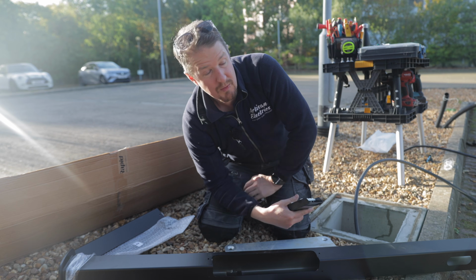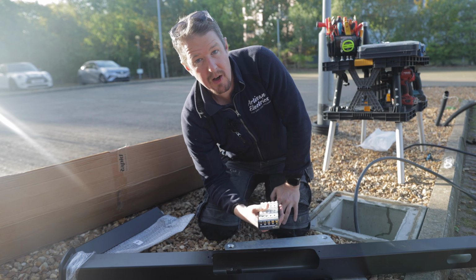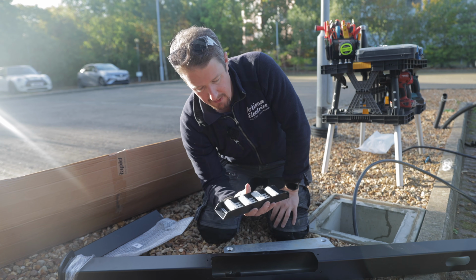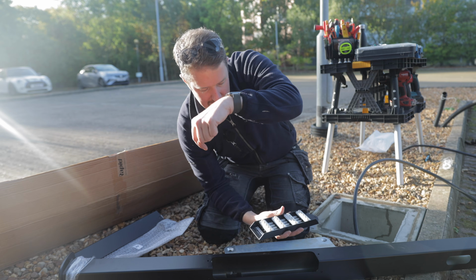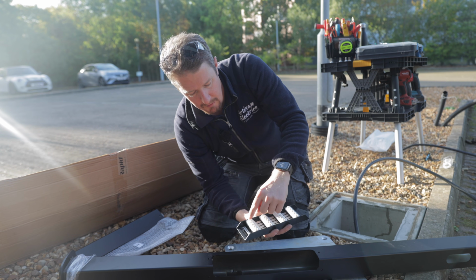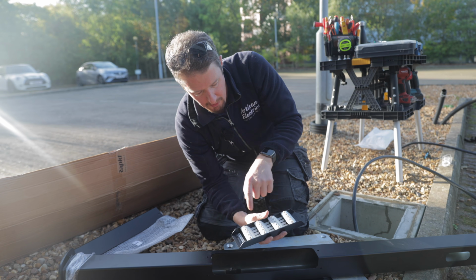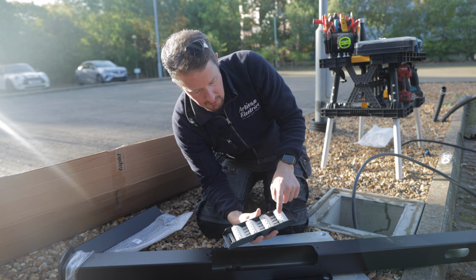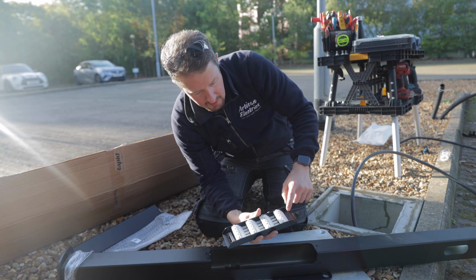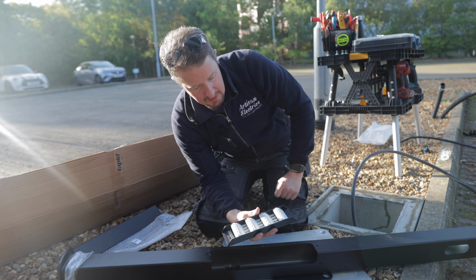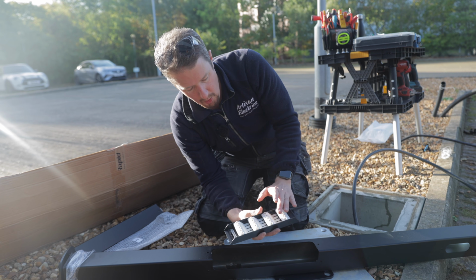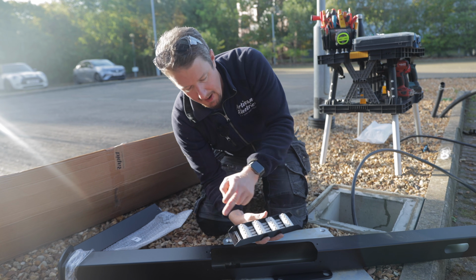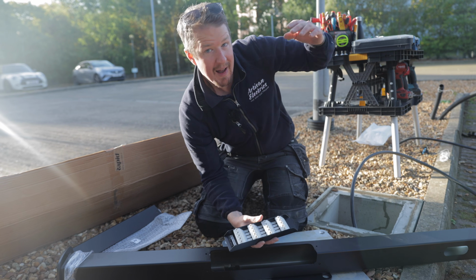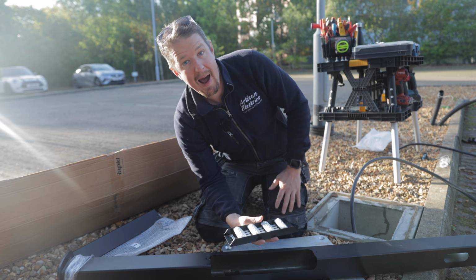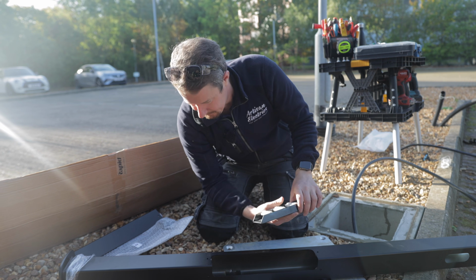But if you do want to run a whole plethora of charging points off one circuit, this device enables you to do that. You basically connect your incoming cable there, your outgoing cable there, then you've got your flex up to your charging point and another flex up to a second charging point, so you can run 1 or 2 charging points off this and then run to another pedestal, and so on. You can just loop in and out almost indefinitely.